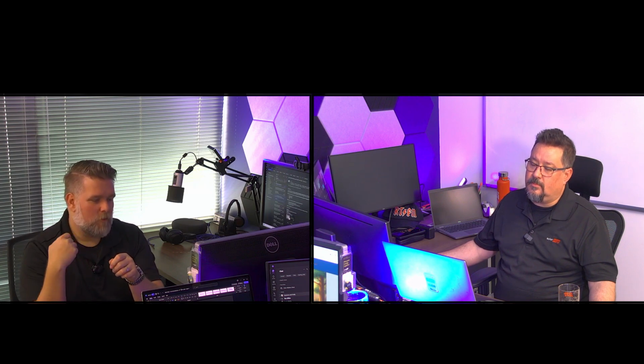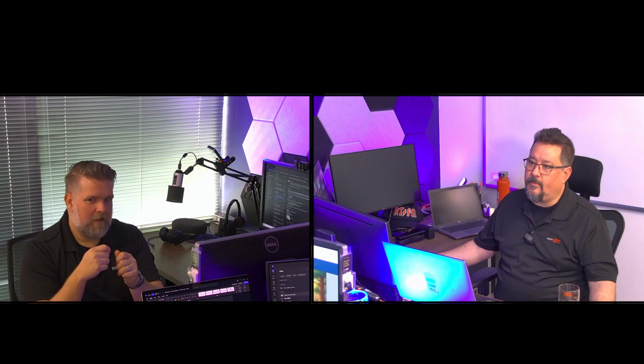Yeah, jeez. Okay, so one of the questions that I get most often is, can support just run a test and see if they can figure out where the isolation fault is before I go out to site? That's a great question. I get this question a lot too. And no, the short answer is no, we can't run it remotely. The largest reason is when you are detecting a ground fault, you need to isolate your strings because we're checking an impedance value, right? And if all of the strings are in, it's going to give us the wrong value.